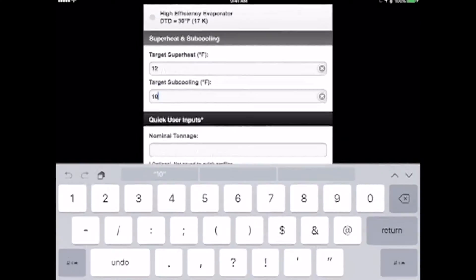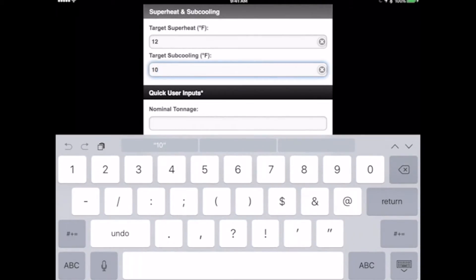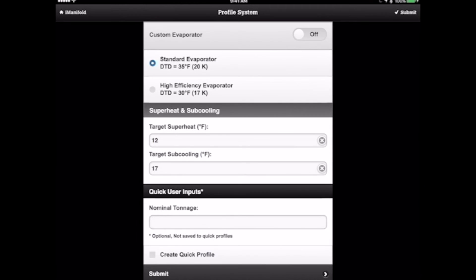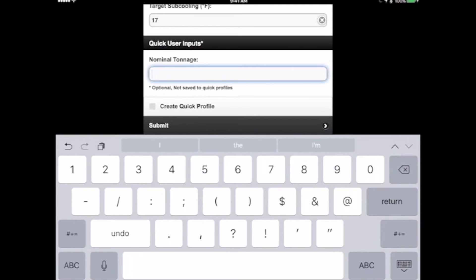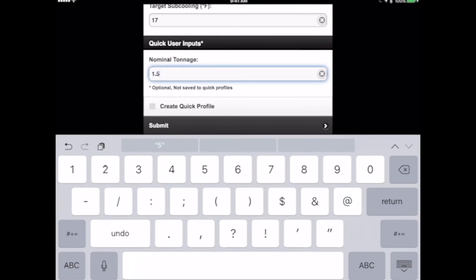To change the target subcooling, you just tap it. It'll pull up the display, a keyboard. We'll put that in there. And then we're going to enter in our nominal tonnage here at 1.5 tons. Then we have an option of either creating a quick profile or simply submitting it.